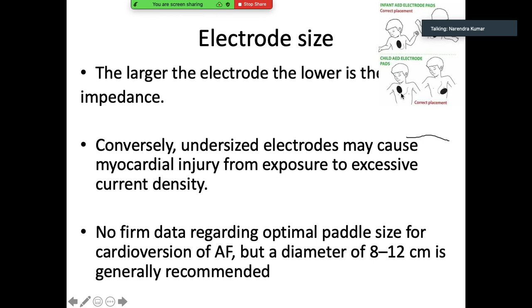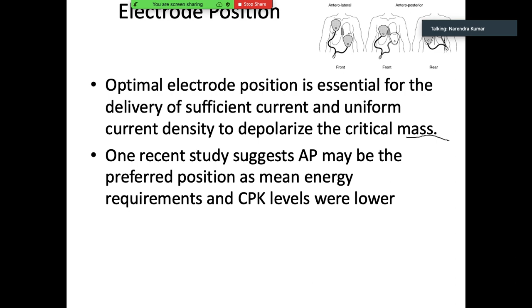As you can already see about the placements, there is antero-posterior over here, and then comes anterolateral. We'll show that further. About the electrode positioning, as I already said, the optimal electrode position is very important, especially for the delivery of sufficient current and also a uniform current density to be able to depolarize the critical mass. In fact, studies have shown the anteroposterior may be the preferred position, as mean energy requirements and the CPK levels were much better as well.